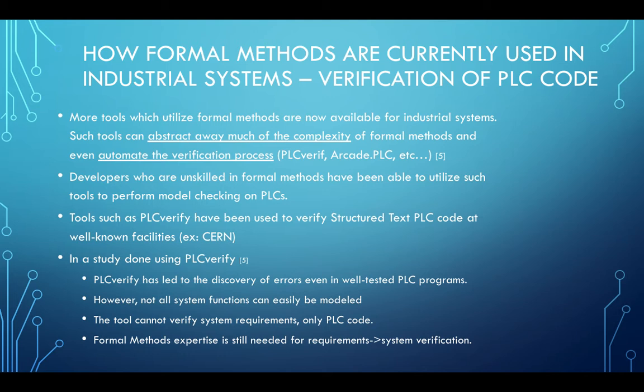And in this study, while I found that the tool could be used to reduce the time it took to perform model checking, it could not be used to model all system functions. And also, as the system is designed to take in PLC code, it's not intended to verify the system at the requirements level. So it certainly has some benefits, but to span the gap between requirements and system verification, further expertise is needed in the area of formal methods. So that's one example.